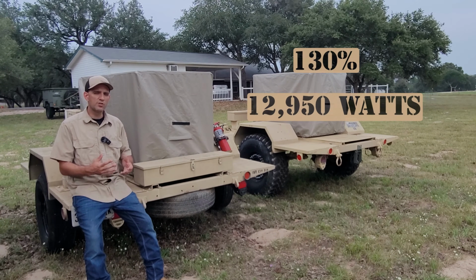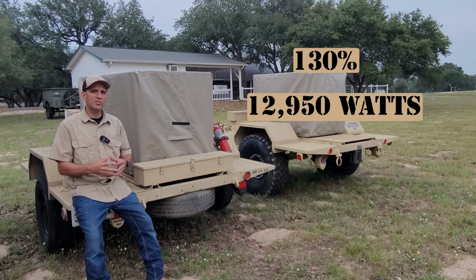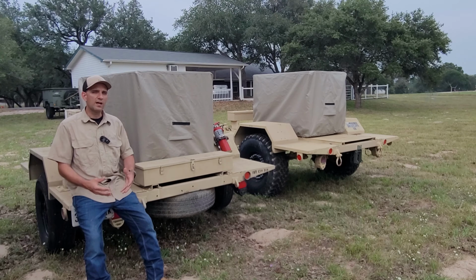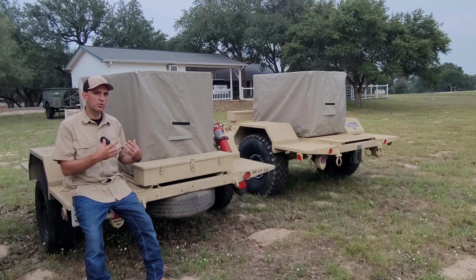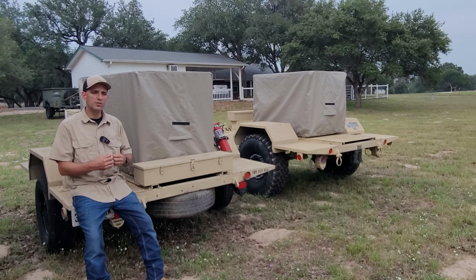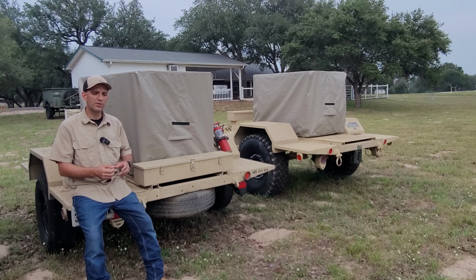When it comes to your devices, if your device is not a 1 power factor, it will usually say so on it, but it might not. That's why when it comes to load banking and load testing, using electric heaters is best, because if you turn them all the way up, they're going to stay on no matter what and just keep making heat. They won't cycle.